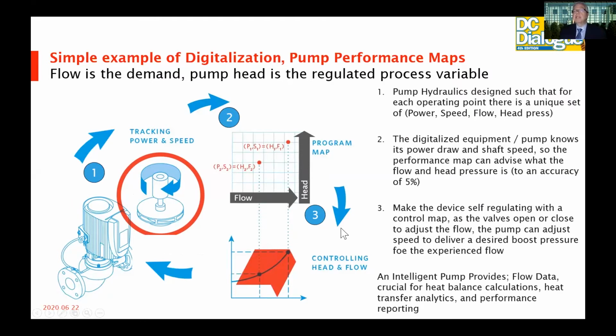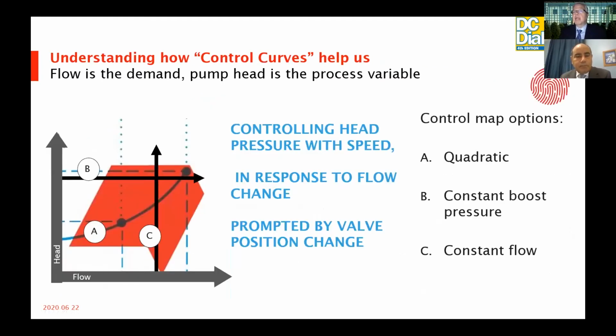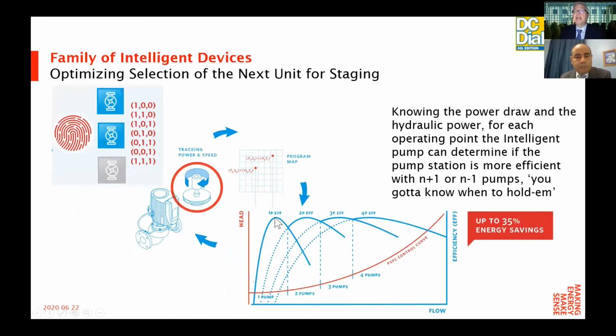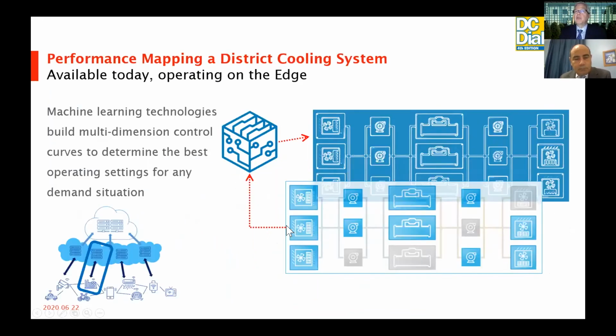So these intelligent devices create an equipment performance map, and I've shown a very simple one here for a two-dimensional pump device where we have flow and head and power and speed. So there's a unique combination for each operating point. So if we know the power and speed, we would know the flow and head. This just gives you an idea of how those maps get created. And that's how we're enabled to know that if we add another parallel device, whether it would be more efficient to add it now or wait a little bit longer or remove it from the duty cycle.